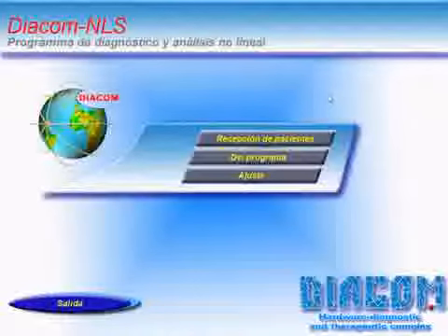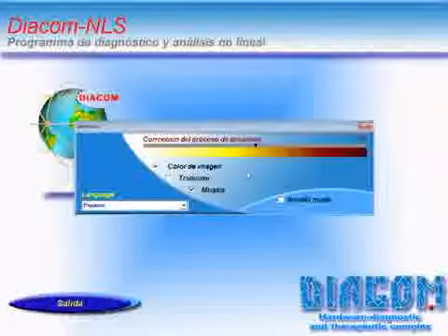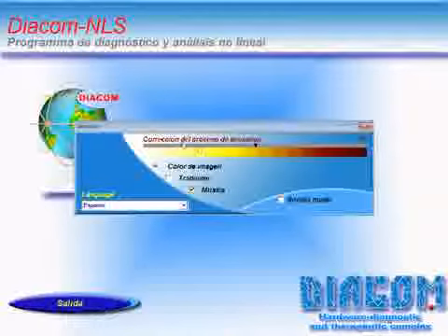So we'll analyze 4 buttons of this window, such being patient reception, about the program, setup, and exit. As hinted, exit button works to terminate. Setup is for equipment configuration. Always, deviation process correction bar shall mark at the middle. It should never be modified, because that thing is only changed by us programmer, and if you ever move that, it could result in deconfiguration of the equipment's sensitivity.